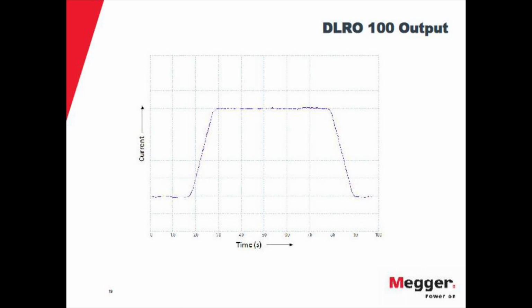Any question? Why would you change the ramp up? Well, if you don't have something that is going to be affected by the ramp, you can do a very quick injection and it's going to be a faster test. If you have a protection system involved in what you are testing, you want a smoother curve so it doesn't trip the protection, and it's going to be a longer test. It's going to increase 15 seconds here, 15 seconds here, plus the time of the measurement, but you are going to be able to perform the test without affecting the system.